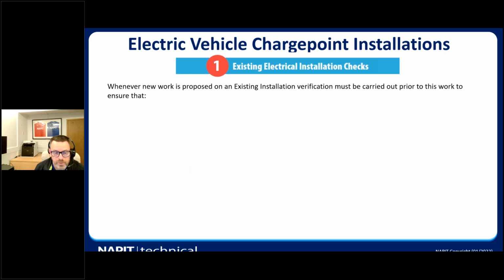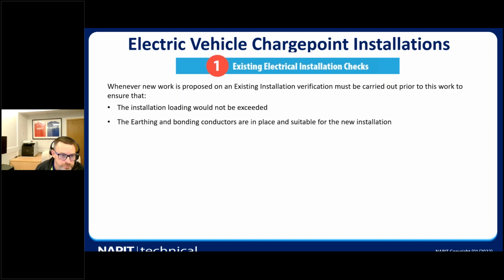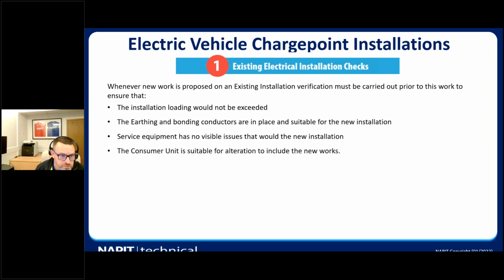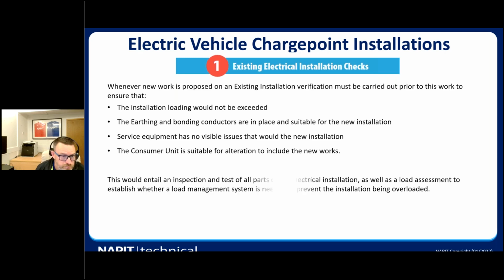So whenever new work is proposed on an existing installation, verification must be carried out prior to that work to ensure that the work can safely be carried out. And we're looking at whether the installation loading would be exceeded by the installation of the charge point. The earth and bonded conductors are in place and are suitable for the new installation. The service equipment has no visible issues that would affect the new installation. The consumer unit is suitable for alteration to include the new works.